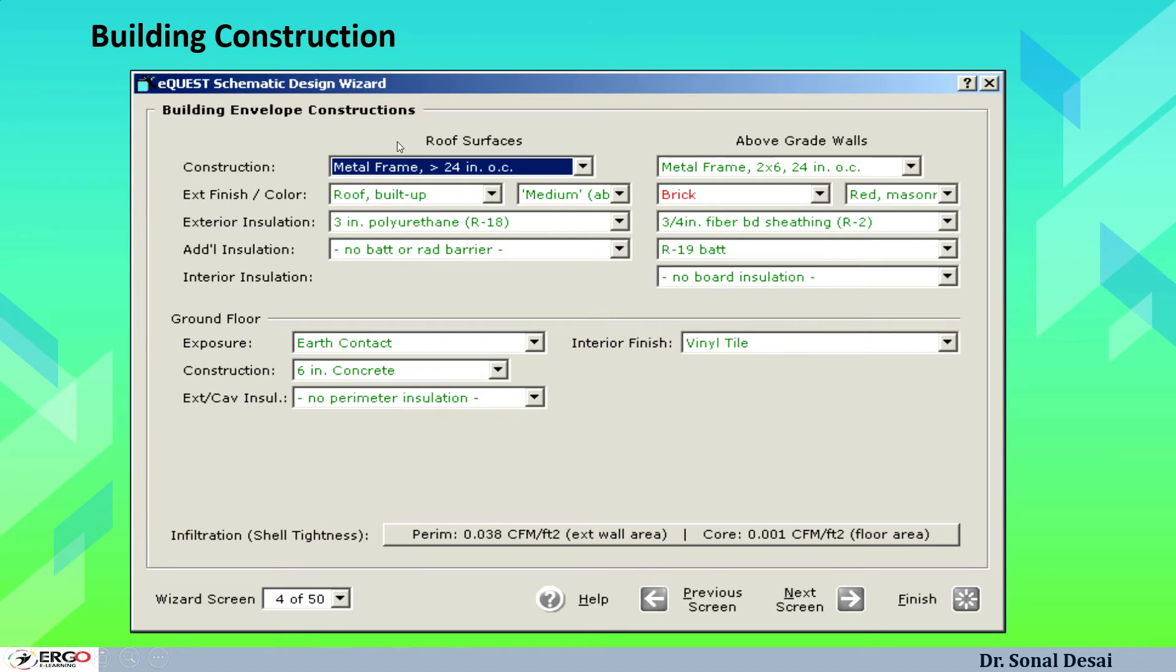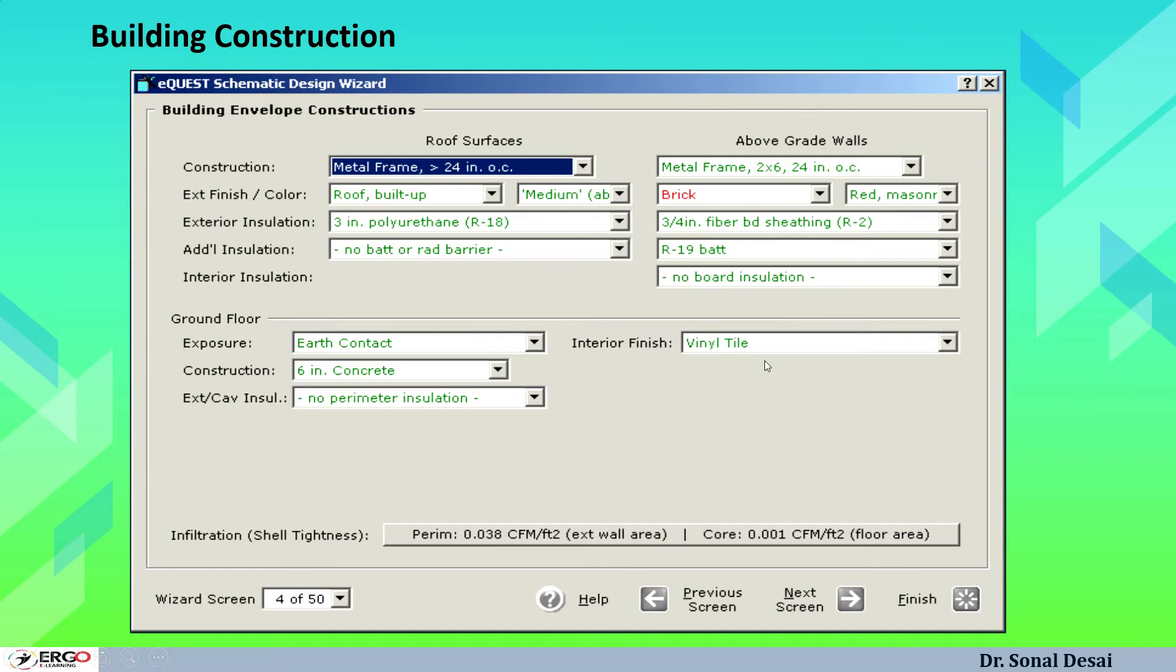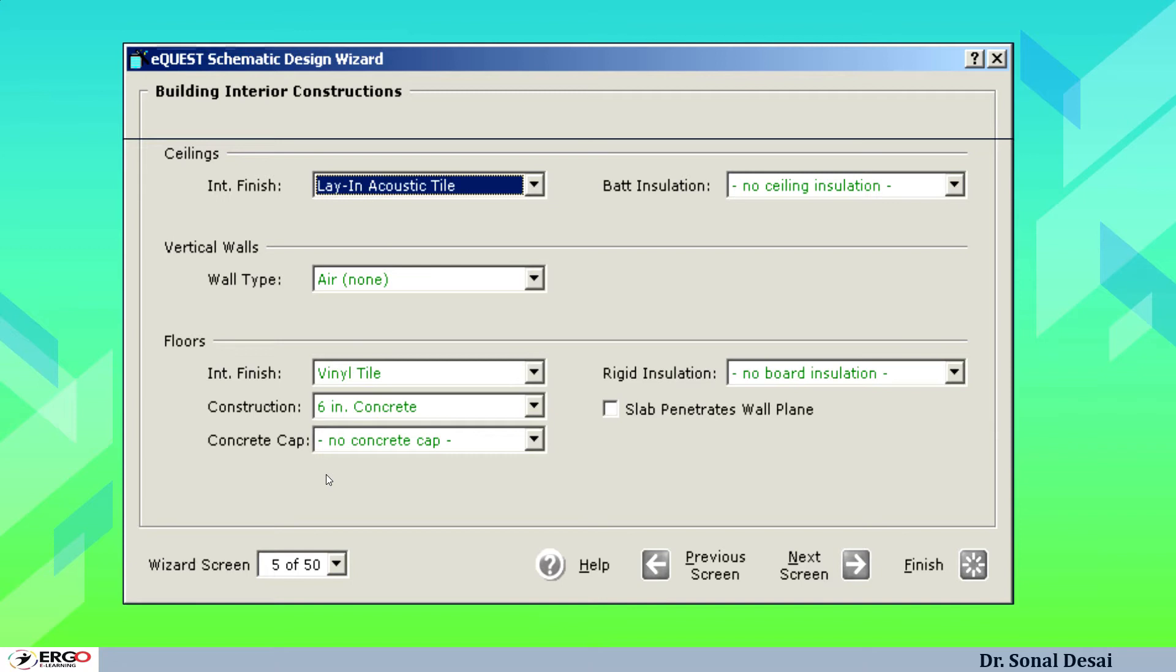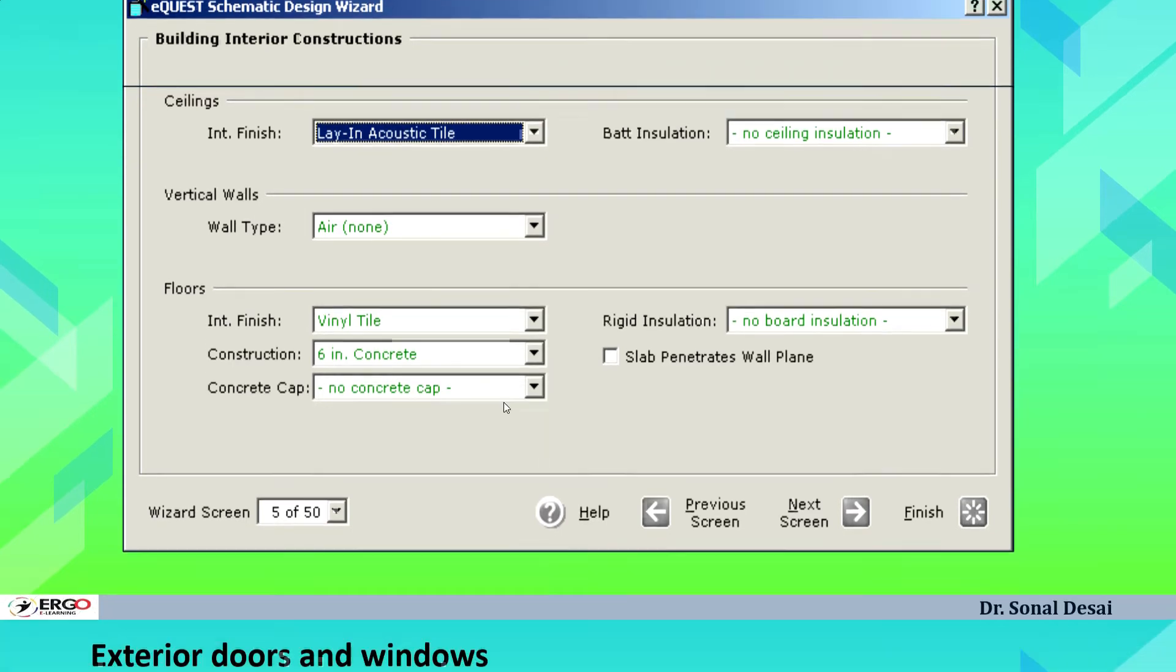When we go towards building envelope, then there are options available to select the material for roof, for the wall, for the ground floor, for the bottom and all these materials can be selected based on internal library. If not available, we may customize them. We can define what is infiltration rate which is related to tightness of the building. Building interior construction also we may define based on the available options like ceiling is of which type, vertical walls are made of what material, what finishes used in floors, etc.